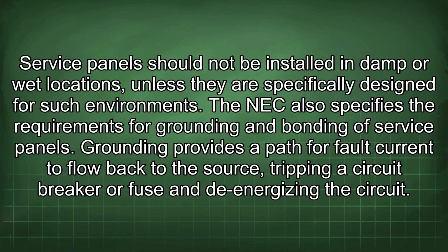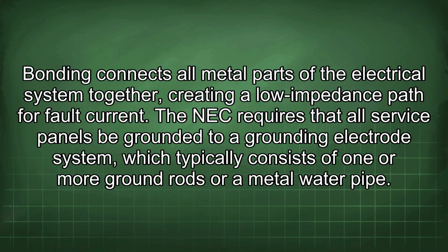The NEC also specifies the requirements for grounding and bonding of service panels. Grounding provides a path for fault current to flow back to the source, tripping a circuit breaker or fuse and de-energizing the circuit. Bonding connects all metal parts of the electrical system together, creating a low impedance path for fault current. The NEC requires that all service panels be grounded to a grounding electrode system, which typically consists of one or more ground rods or a metal water pipe.